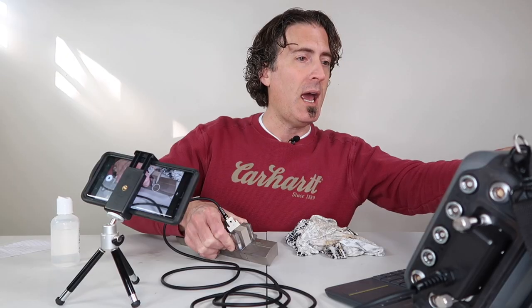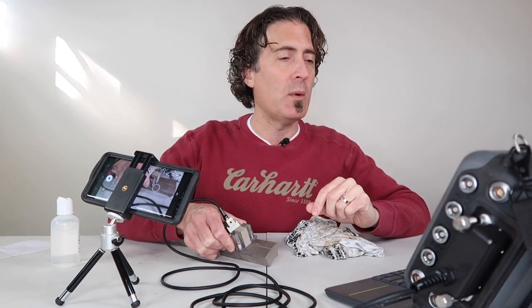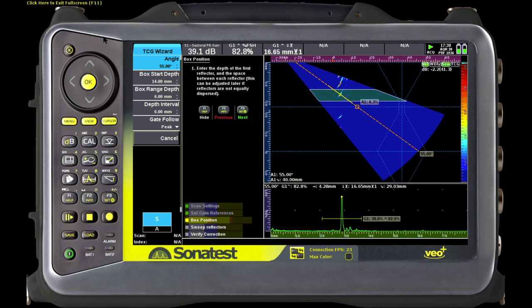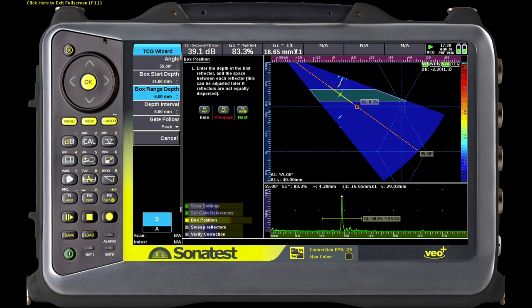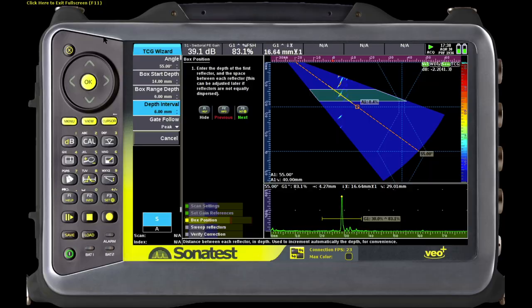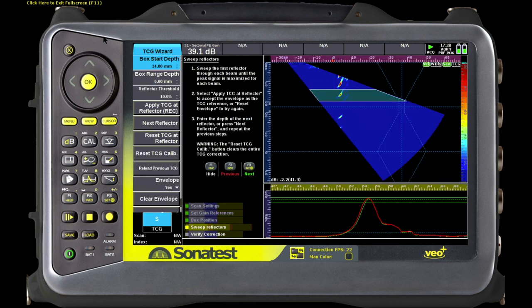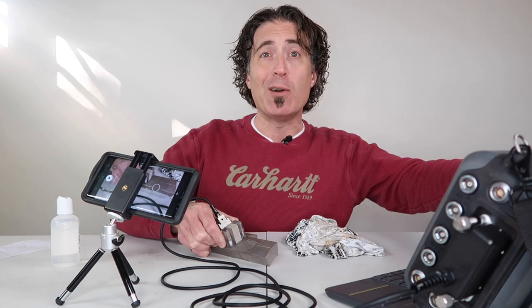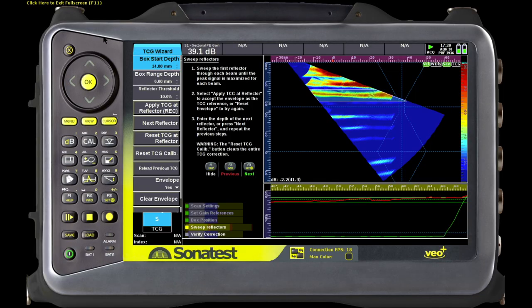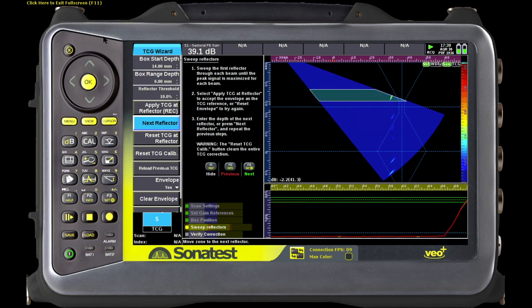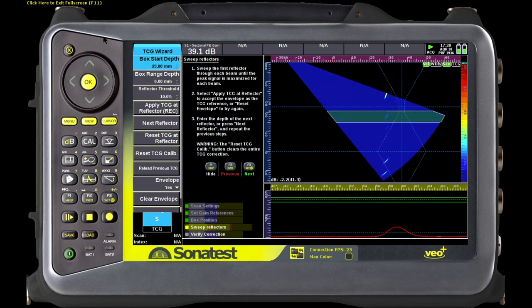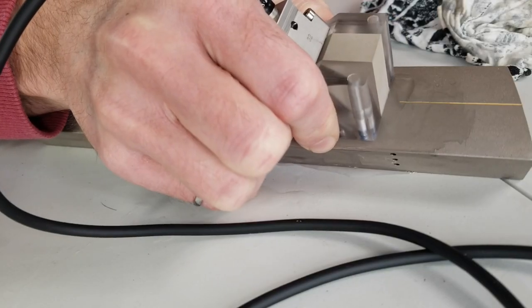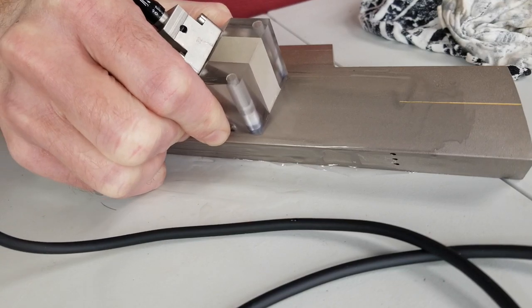You can see it is a little hot, so it just makes it easier if we take that down to 80 percent to start. On a Veo you have a calibration box that spans the width of the S-scan; on an OmniScan you'd use your gates of course. The box start we can move up and down, the box range depth is the size of the box, and the depth interval is how many millimeters it bumps down each time we move to the next reflector — in this case I'm going to use six. We're going to proceed, moving the probe back and forth through all of the angles.